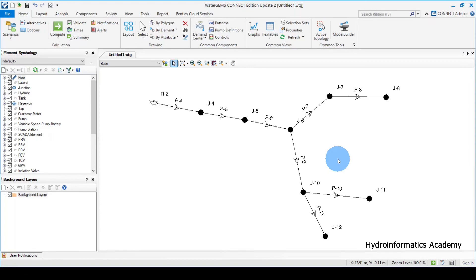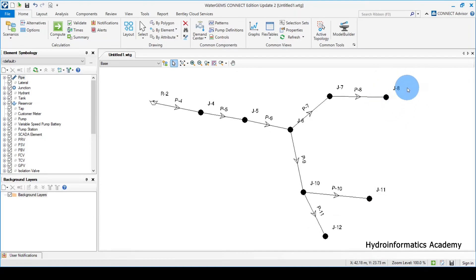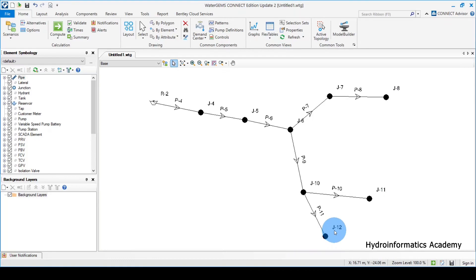The other parameter is pressure, especially at the junction areas where people are assumed to consume water. Within these areas, pressure should be 10 meters of water column, but not above 20 or 30. We need to aim for around 10 meters of water column but not above 20.